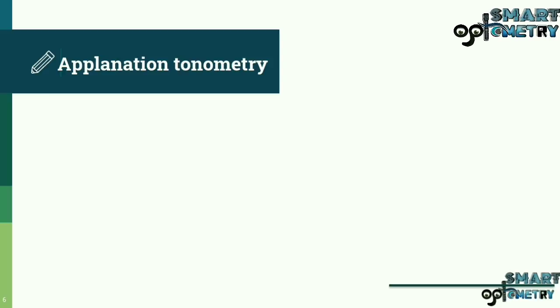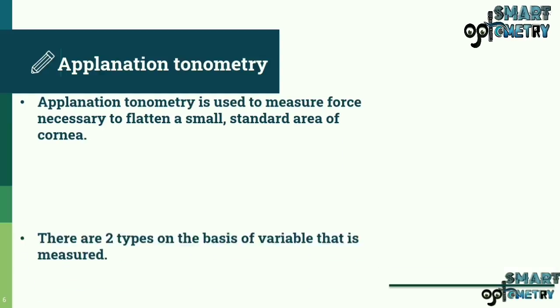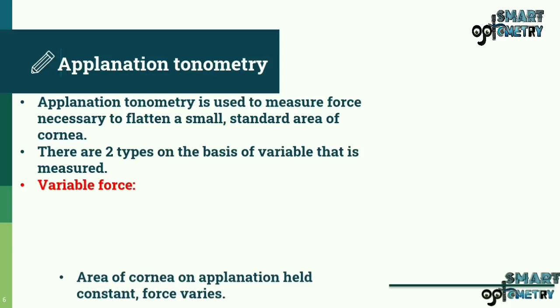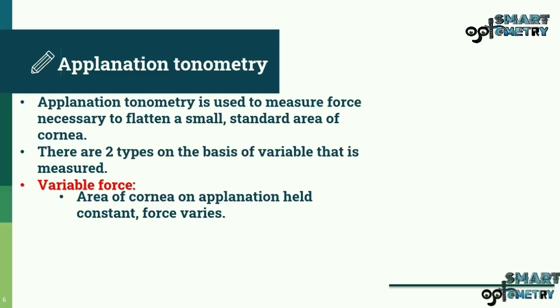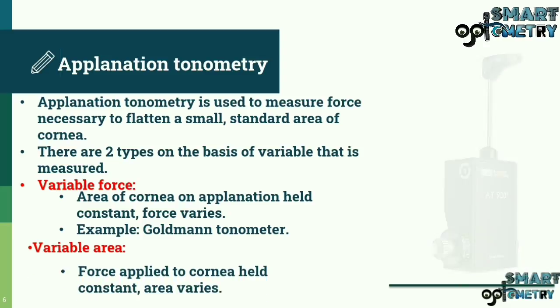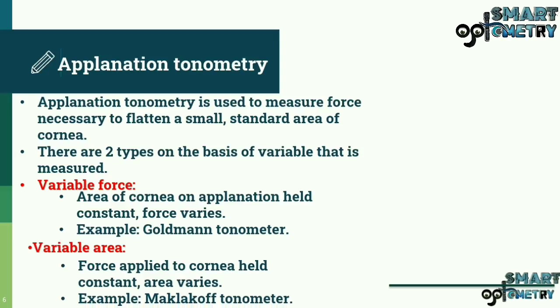Applanation Tonometry is used to measure the force necessary to flatten a small standard area of the cornea. There are two types based on the variable that is measured. In variable force type, the area of cornea on applanation is held constant while force varies — e.g., the Goldmann Tonometer. In variable area type — e.g., the Maklakov Tonometer.